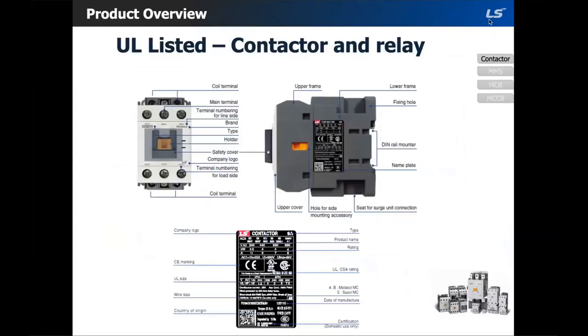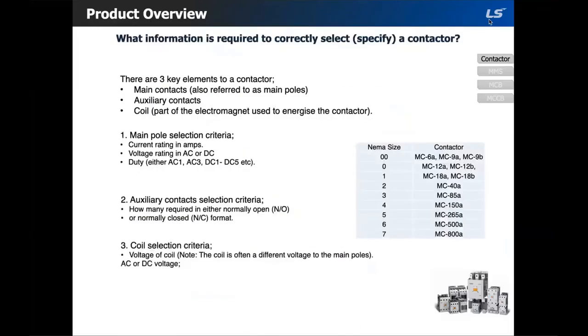So let's look at the nameplate. I think someone else requested us putting a NEMA size rating on the nameplate, but I don't think we have the rating on the nameplate here. Would you say it would be crucial to have a NEMA rating on the nameplate? If it's a contactor and an overload joined together as a motor starter, people are looking to see typically on the contactor NEMA 1, NEMA 2, NEMA 3. For instance, we sell to Motortronics in Florida, and everything they get has to have a NEMA rating on it. So when they use a starter, which is the contactor and overload, it has it on it.